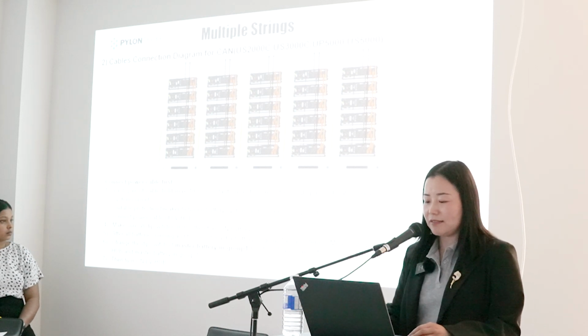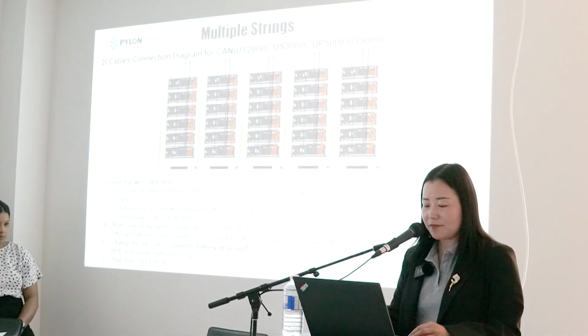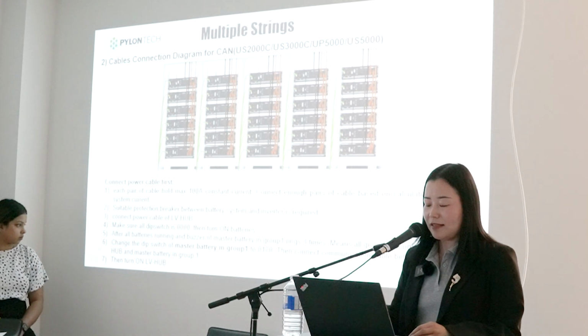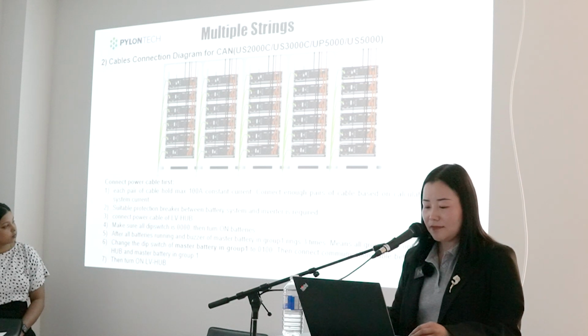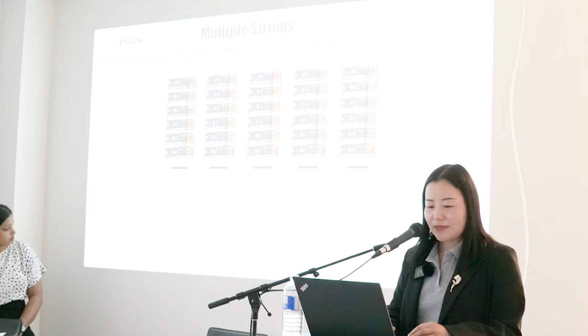Then the address of the LV hub must be 0001. 4. All address dip switches of the batteries are default. 5. Boot up every single battery with the soft switch button in sequence, first the master batteries. 6. Change the dip switch of only the master battery in group 1 to 0100. Then turn on the LV hub.